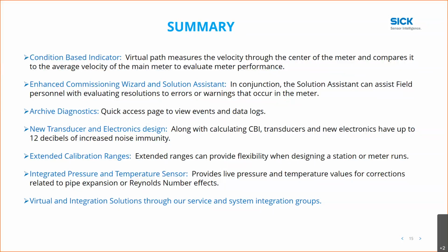New transducers and electronics, along with calculating the CBI, the transducers and electronics have up to 12 decibels of better noise immunity. Extended ranges can provide flexibility in designing of the meter and meter runs. And of course, the integrated pressure and temperature sensor that is now mounted on the meter body of the XT meter provides live pressure and temperature values for corrections related to pipe expansion or Reynolds number effects. This is a lot of data that's available in the meter.